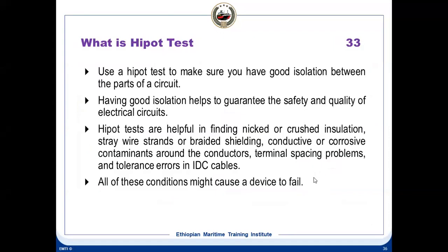Another test is called the HIPO test. This is called the high potential test. The high potential test is to make sure you have good isolation. Normally you do a continuity test. Why do you do a continuity test? To see that the cable is good. The high potential test is to check that you have good isolation between two parts of a circuit. It is just the opposite of the continuity test. We are doing a continuity test for a cable every time, to see that the cable is good from this end to that. The HIPO test is to check the insulation. How good is your insulation?